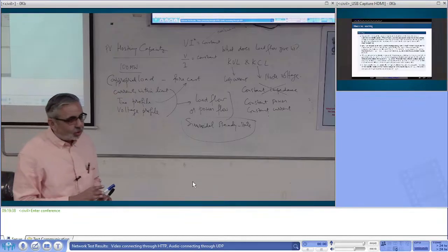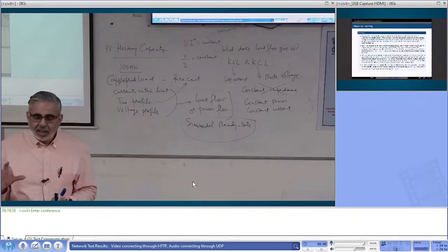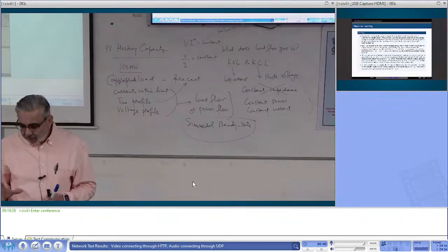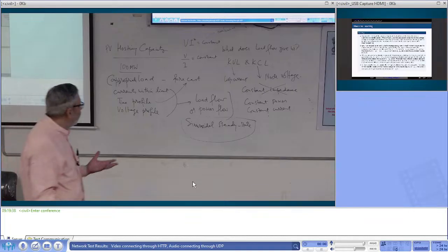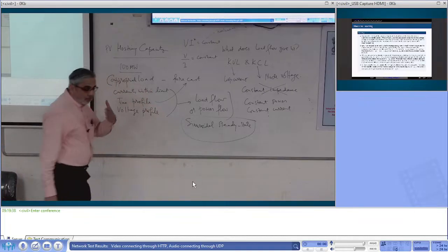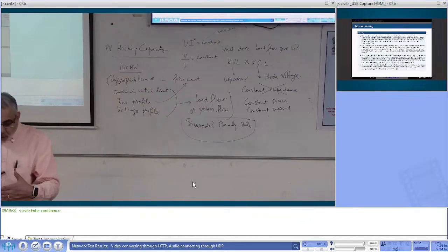There is a lot of trouble with hosting capacity. The biggest trouble is, what is the definition of hosting capacity? The one we use is that we have got 100 megawatts. There are hosting capacity algorithms which take 100 megawatts but put all of it on a single bus and do the analysis.